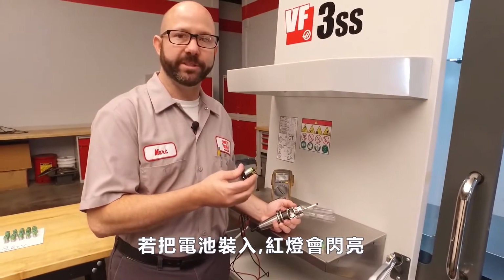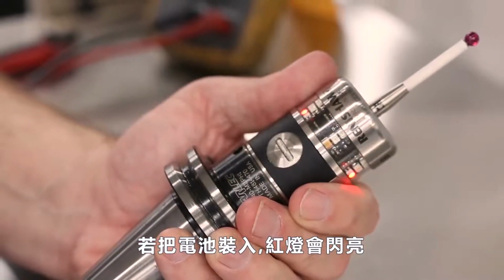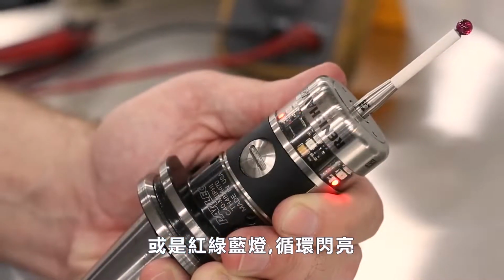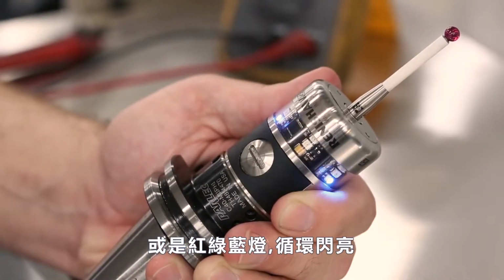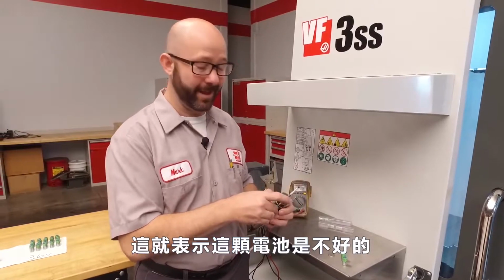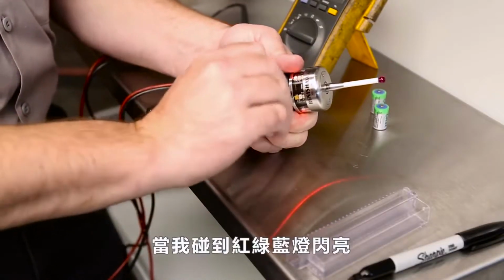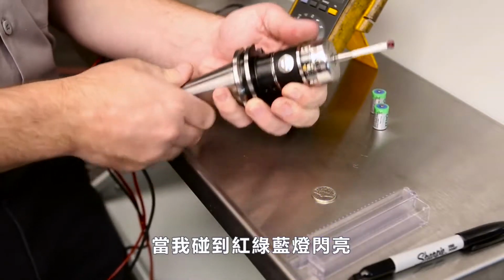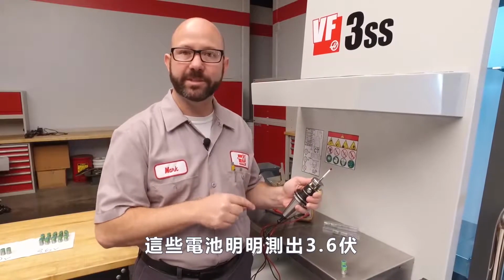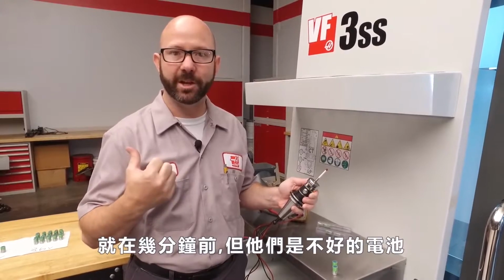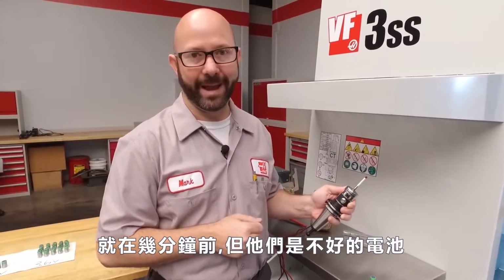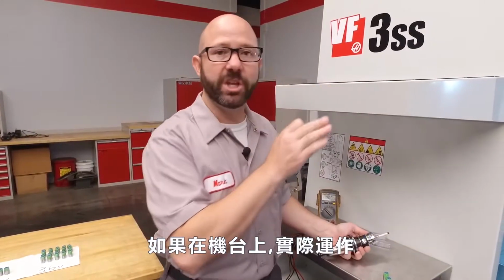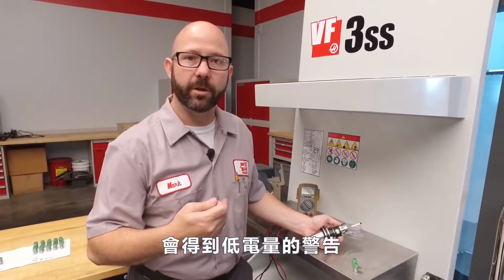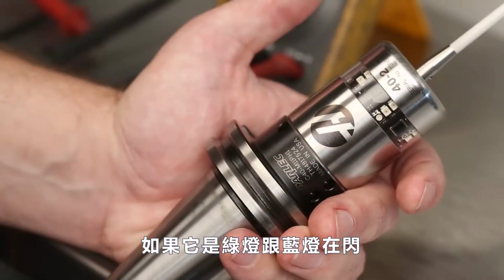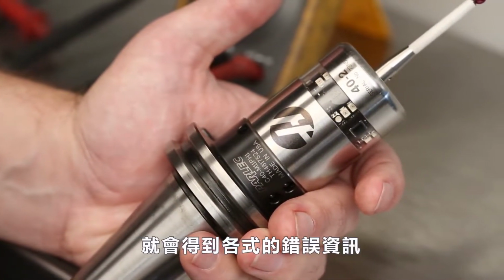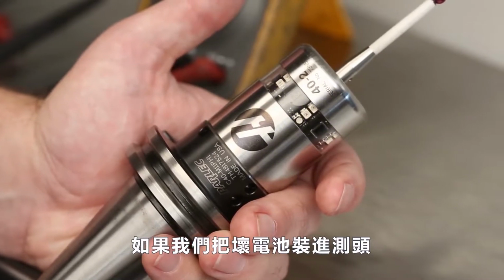Now, if I put these batteries in and I get a flashing red light or a flashing red, green, blue light where it cycles that over and over again, that means that these batteries are bad. And it looks like I'm getting a flashing red, green, blue. These batteries that measured 3.6 volts just a minute ago are showing up as bad. Now, if we had been in the machine, actually in cycle, and we got a low battery alarm, it would typically flash green and blue. So you can get all kinds of errors if we put bad batteries into our spindle probe.